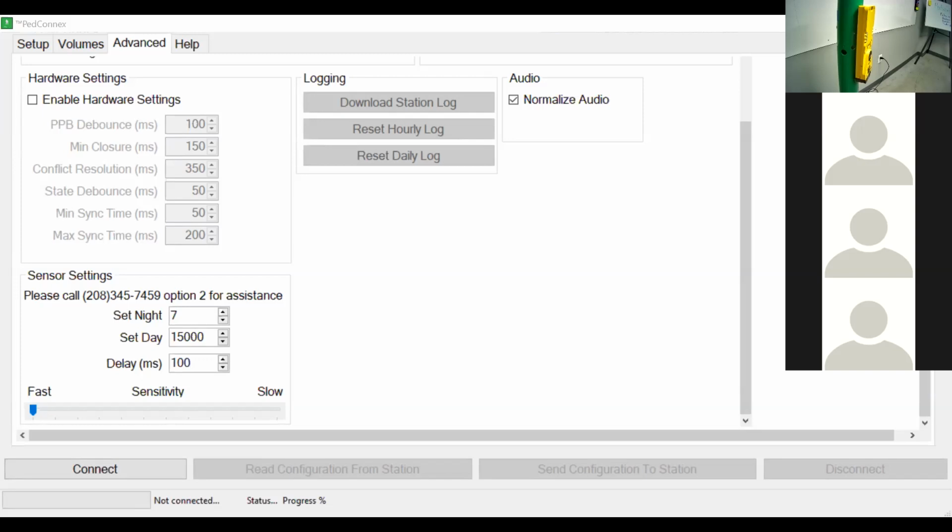One of the biggest issues we have with the Polara Navigator buttons is that in the City of Tampa, a lot of our mainline intersections, we keep our main line on recall. So it's not pedestrian activated. It just comes up with the green. Right. And I know their buttons, like yours, the voice wait comes up when the button is pressed. But if I put the intersection on recall, will the button automatically say wait for visually impaired pedestrians, or is that only when the button is pressed?